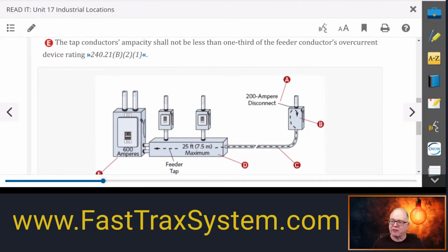The point here is that the 25 foot tap conductor has to stop and terminate into an overcurrent protective device, either a circuit breaker or fuses. Beyond that, it can feed whatever the load calcs you've determined, however many overcurrent devices you need. You have to think about your system design. But as far as the 25-foot tap rule, we're done when it hits that.